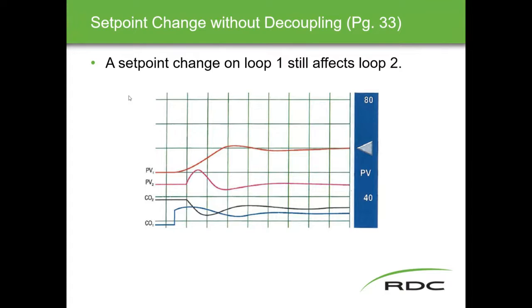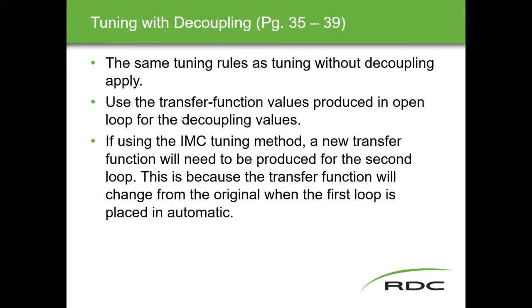The next slides show what happens with and without decoupling, and when loop gain is greater or less than one. First, a set point change showing reactions of both loops without any decoupling: a step change on controller one causes a response in both PV2 and PV1. Obviously no decoupling at all — a change in one controller changed both variables. The whole point of decoupling is that at minimum one variable should stay steady.